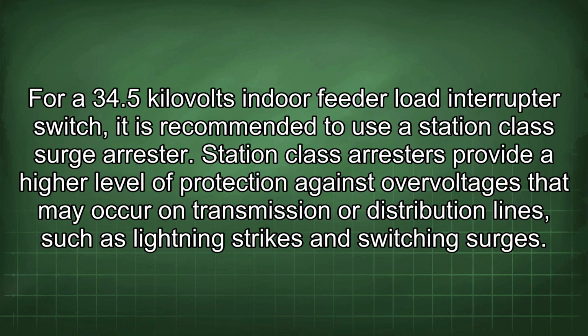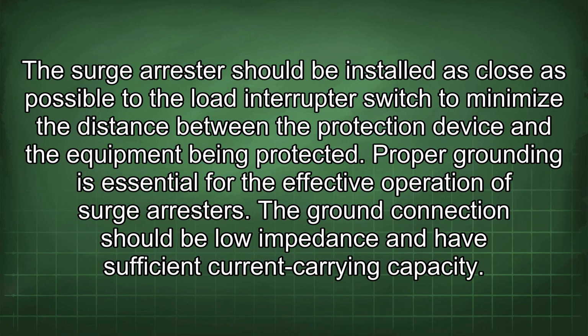For a 34.5 kV indoor feeder load interrupter switch, it is recommended to use a station class surge arrestor. Station class arresters provide a high level of protection against overvoltages that may occur on transmission or distribution lines, such as lightning strikes and switching surges. The surge arrestor should be installed as close as possible to the load interrupter switch to minimize the distance between the protection device and the equipment being protected.